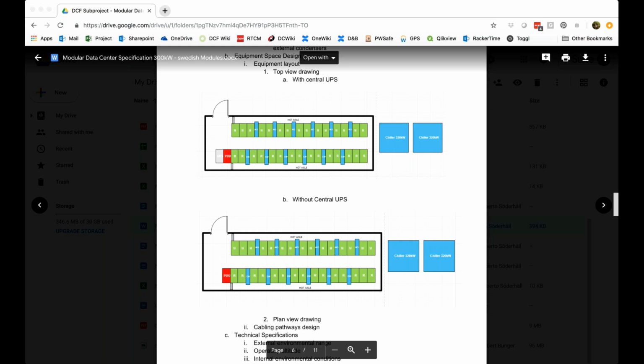I think we could manage to take in the pipes on one side and have the door in the cold aisle and get the infrastructure not interrupting the fire escape way. Yeah, we can do that. So I put in an extra door. Yep.